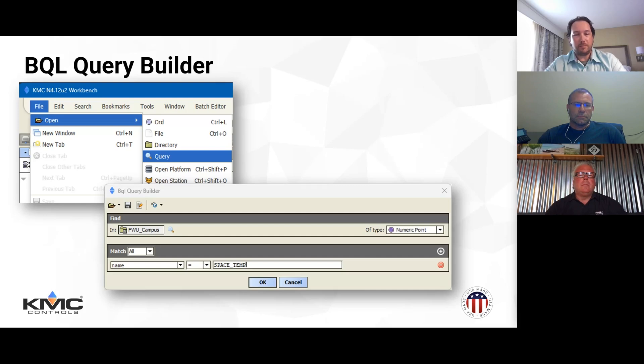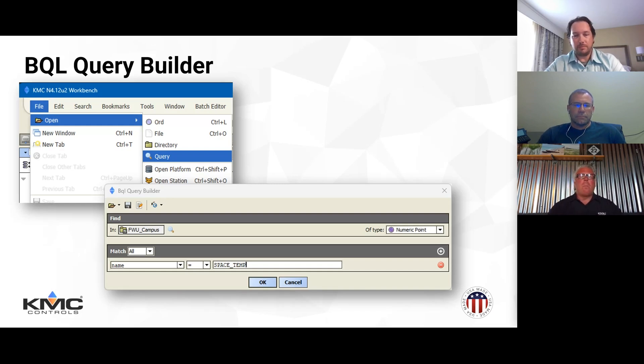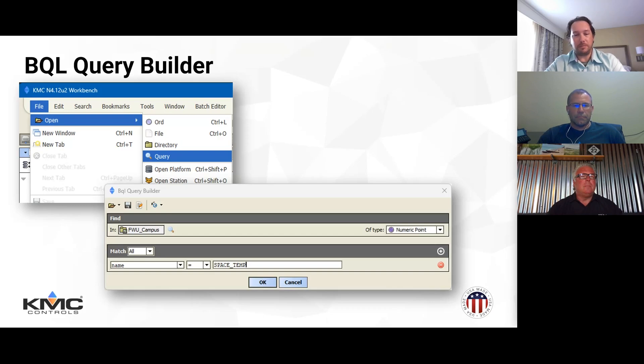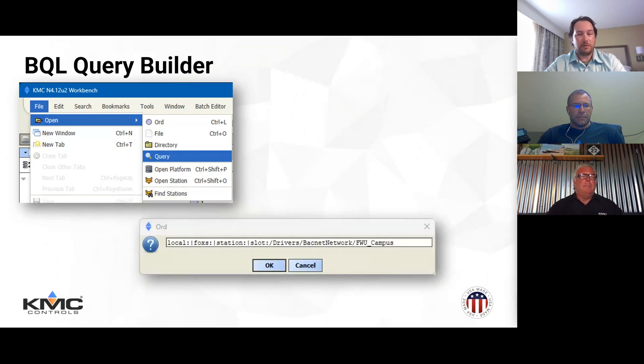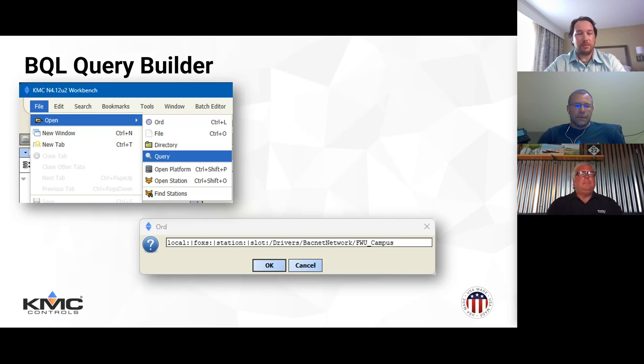The 'Of Type' selection allows the user to specify the extent of the BQL query - for instance, if you're looking for specifically a numeric point or Boolean point. Under there, the 'Choose Columns' area lets you specify the projection of the BQL query to narrow it down. The 'Match' area lets you specify the predicate. Once the search is submitted, it pulls up a generic table view. Alternatively, on any screen you can get to a BQL query in string format using the ORD file menu command or the Control-L hotkey.